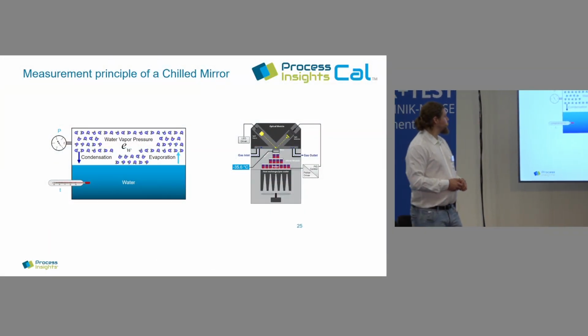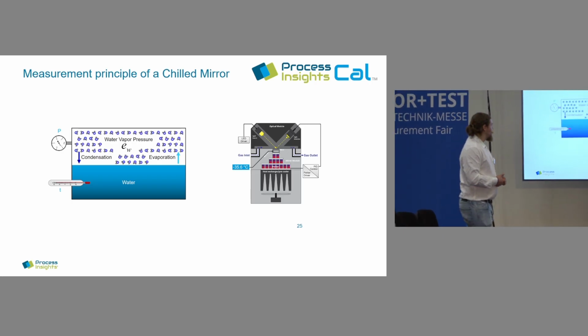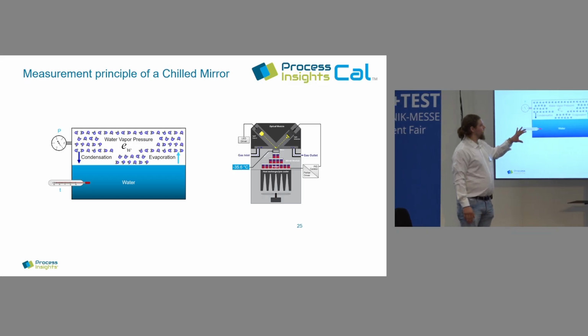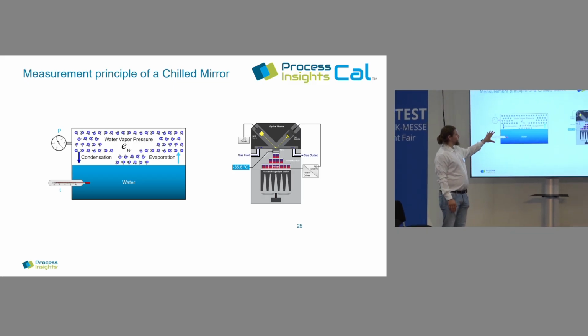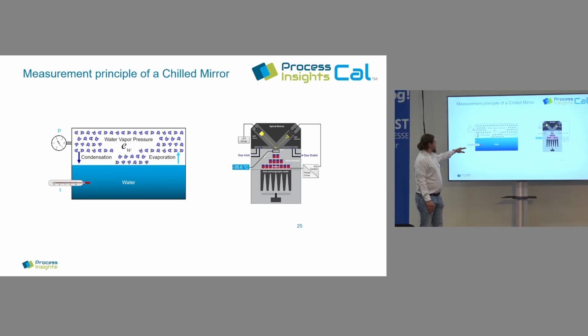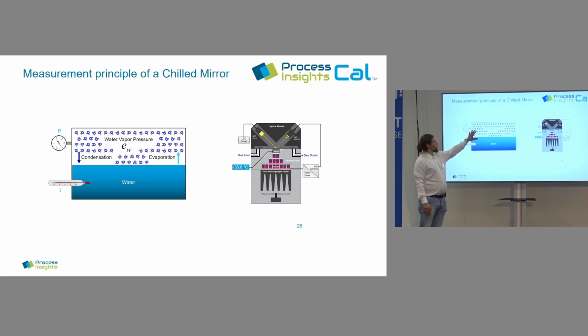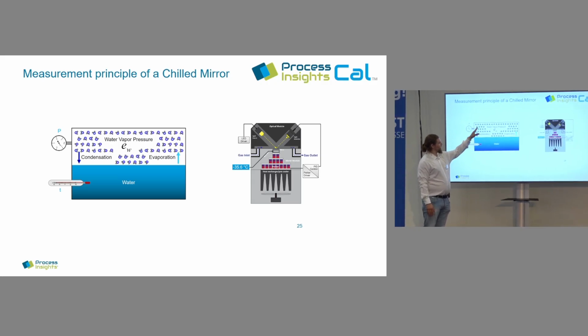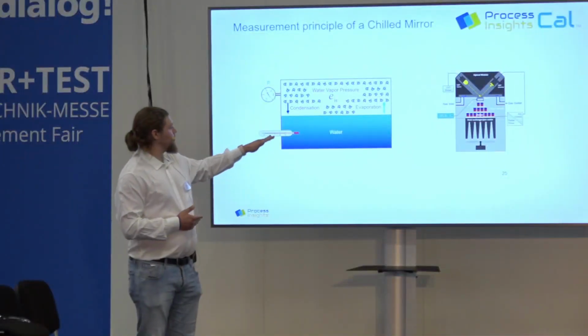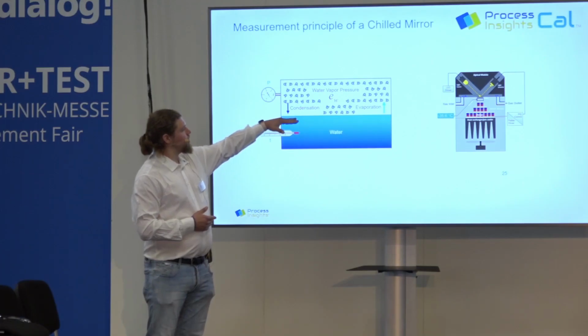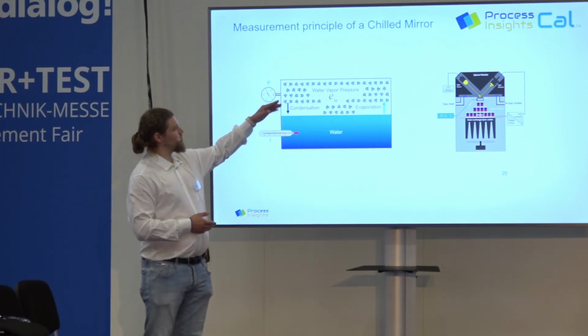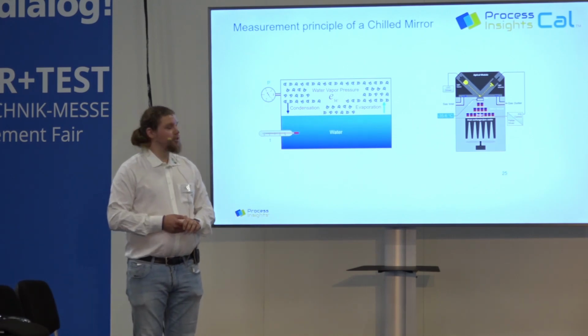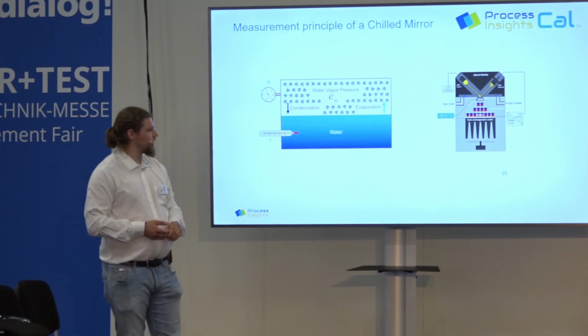So our chilled mirrors, here we can have an overview of how they generally work. From the physical point of view, the basics are that we have a vacuum chamber and we put a liquid inside. Here it's water. Based on the temperature of the water, there will be moisture also evaporating to the gas above so that we can measure a pressure. And at the dew point temperature, this is a fixed value. So we have temperature, pressure, and the absolute content of H2O fixed together. So if we measure the temperature here, and we know the pressure, then we know also the absolute content of water in the gas.